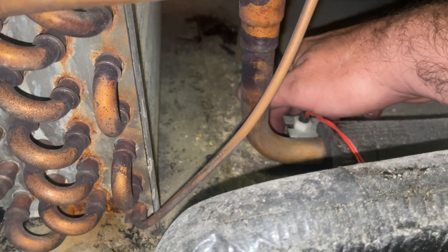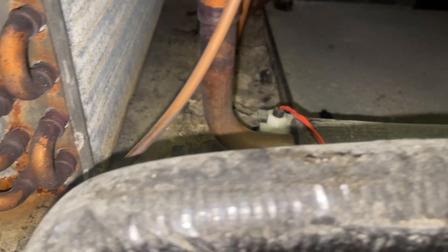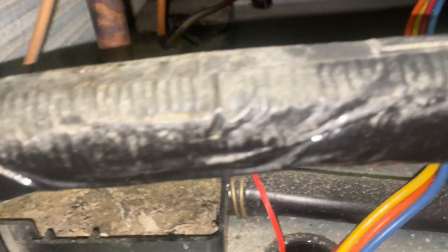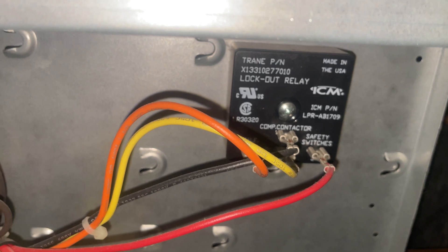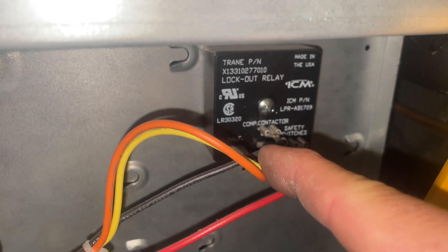A clogged drain pan trips the float switch, and once it trips the float switch it hits the lockout relay. The lockout relay can only be reset by removing 24-volt power and then reapplying it, so this thing's just been running non-stop. Here's our lockout relay — this yellow and orange wire goes to the contactor.